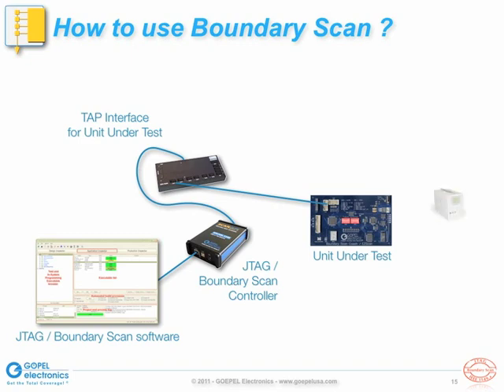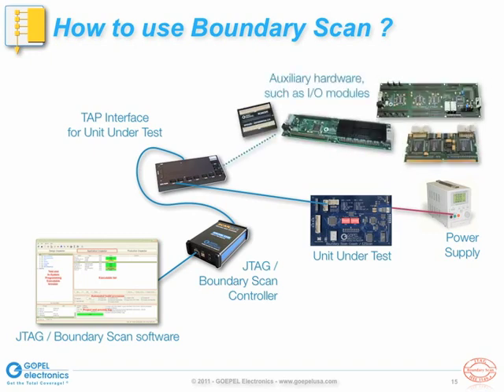As mentioned earlier, boundary scan testing requires the UUT to be powered up, so the tester setup also needs to include a power supply for the UUT. A test system may provide additional boundary scan I/O channels and other digital and mixed signal I/O for the verification of UUT interfaces in order to extend the test coverage achievable with boundary scan on a particular UUT. Such I/O modules are available in a variety of form factors and feature sets.